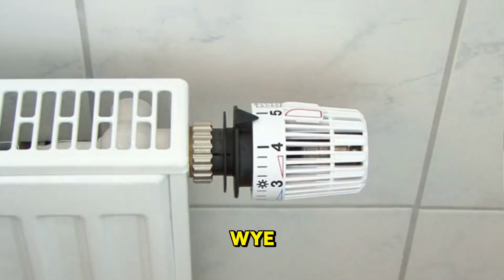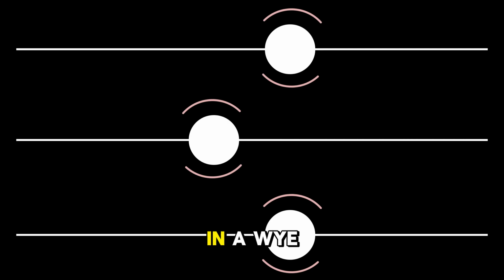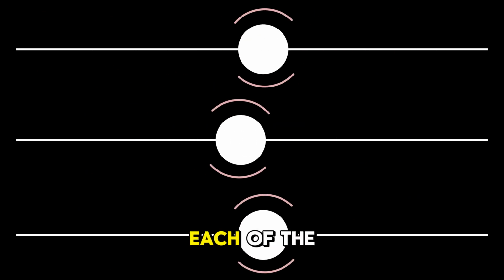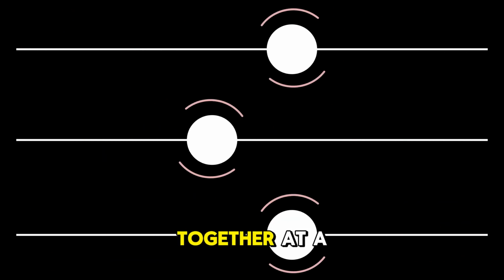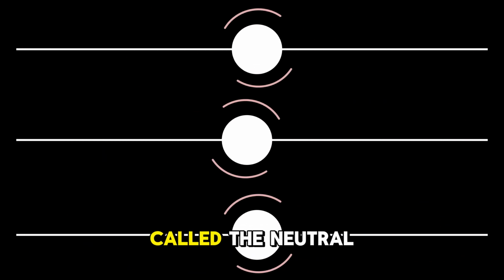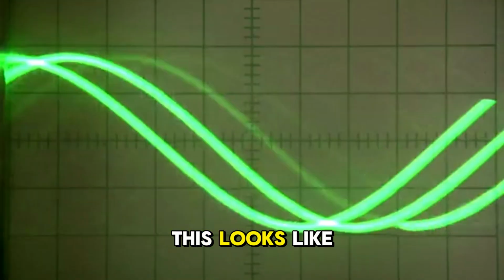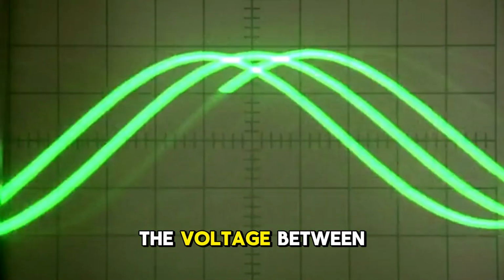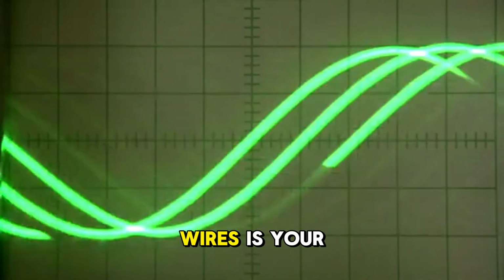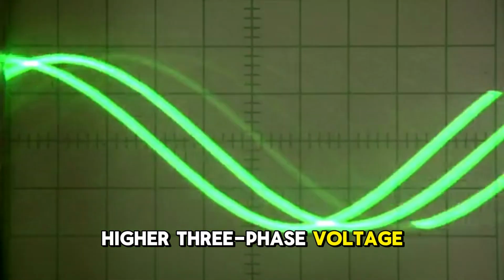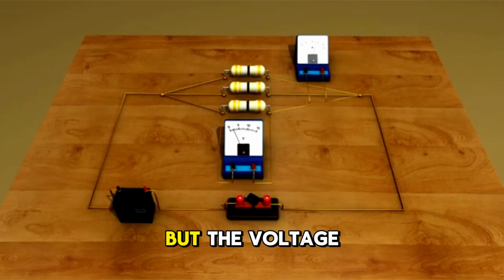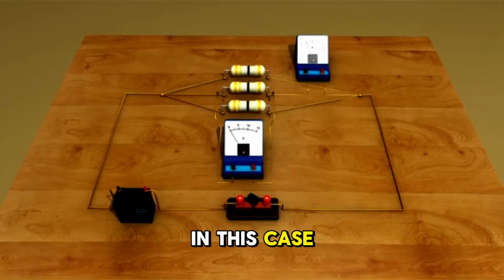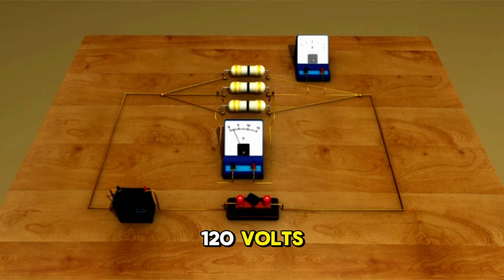That's where the Y configuration comes in. In a Y setup, one end of each of the three coils is connected together at a central point, called the neutral. This looks like the letter Y. The voltage between any two of the outer phase wires is your higher three-phase voltage, like 208 volts. But the voltage from any phase wire to that central neutral point is lower, in this case, 120 volts.